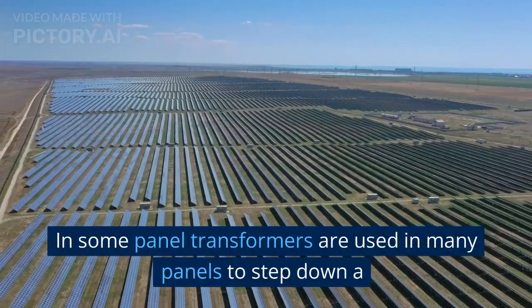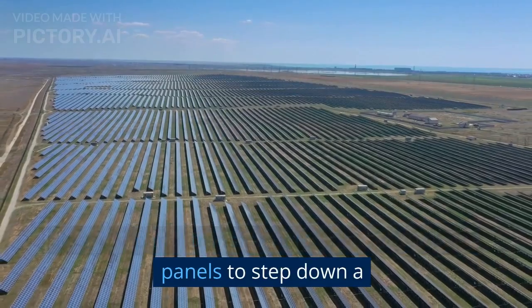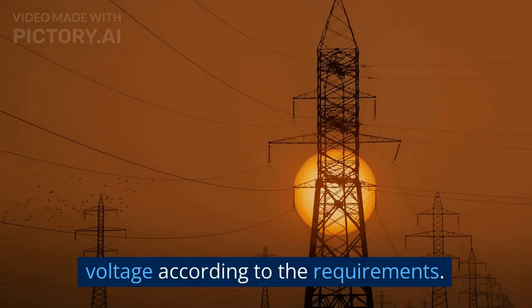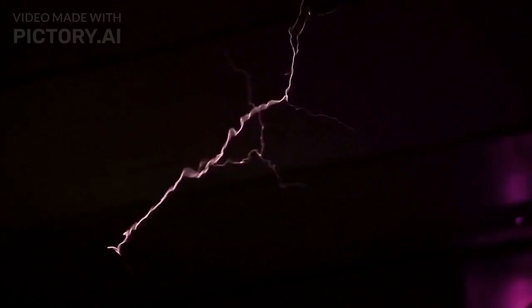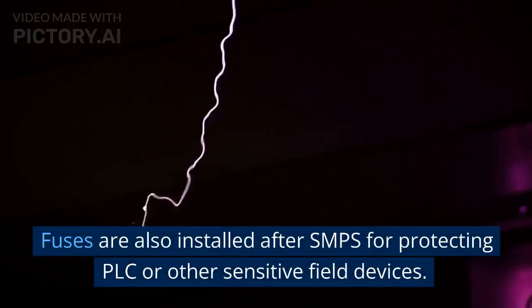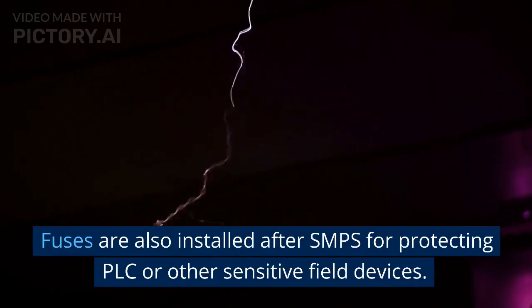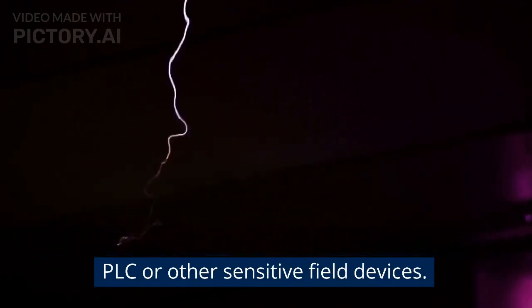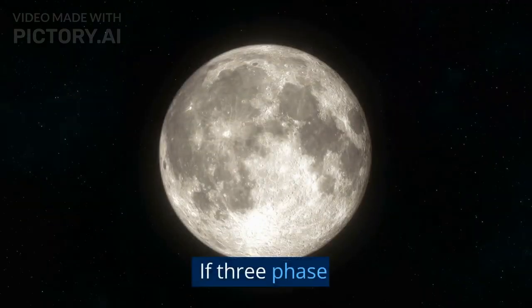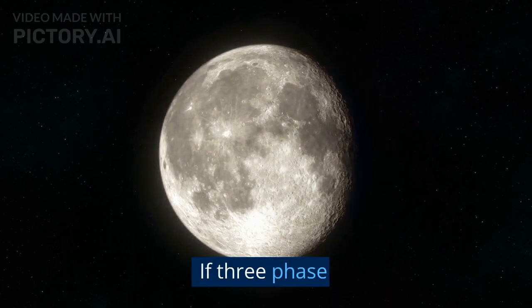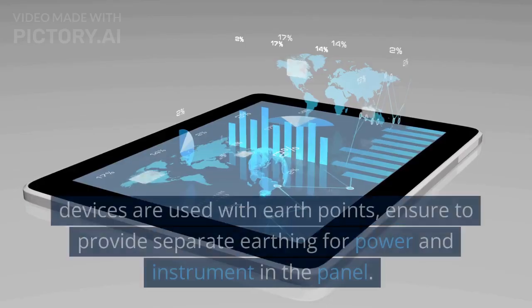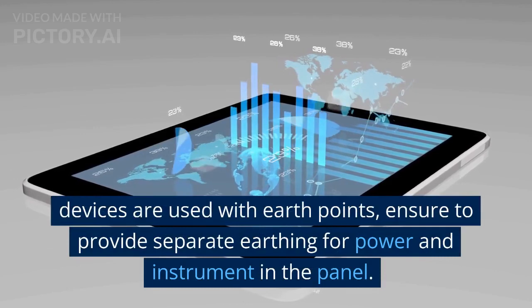In some panels, transformers are used to step down voltage according to the requirements. Fuses are also installed after the SMPS for protecting the PLC or other sensitive field devices. If three-phase devices are used with earth points, ensure to provide separate earthing for power and instrument in the panel.